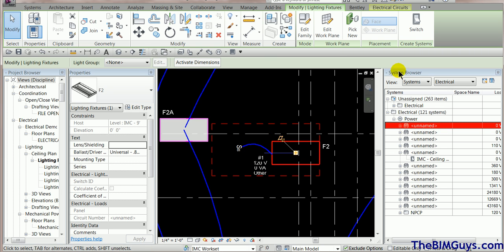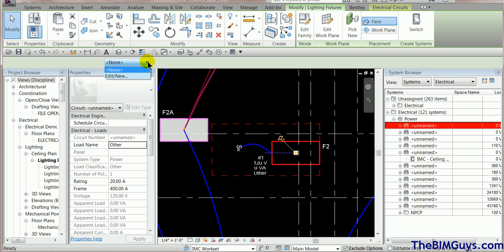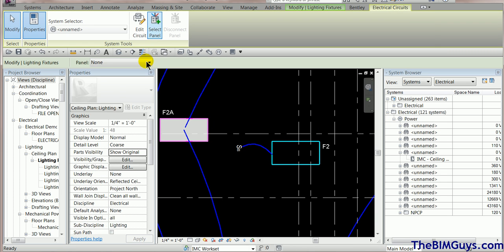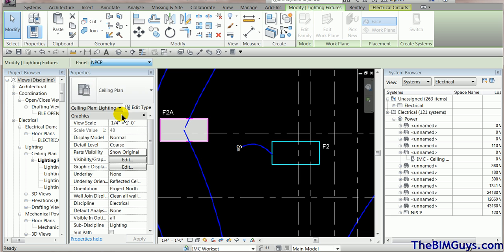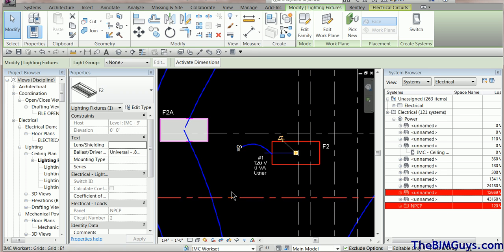Some of these fixtures aren't plugged in anywhere — no power because they're not going to any panel. You can circuit things without sending them to a panel, and sometimes early on that happens. We create a group of electrical receptacles or light fixtures but never really power them up. Make sure things are sent to the panel so you have a true load. Go to Electrical Circuits, hit Select Panel, drop down the list, choose the panel, and now it's actually circuited to a panel. It won't be unnamed anymore.